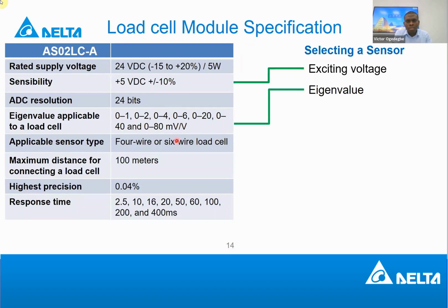So we have a question. Yes, that's a good question. Yes, Shami, you can connect two load cells to one channel in order to get an average weight value. You connect them together, then you connect them to one channel, and then what is measured is averaged. The advantage is that it helps you have a balanced reading, a reading that is not distorted, if you combine two together. You can do that for 4-wire type of load cell and for 6-wire type of load cell. It's possible.